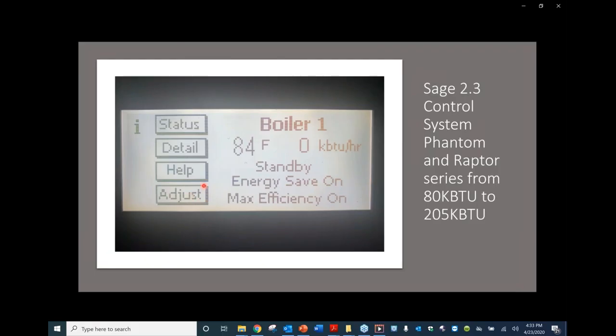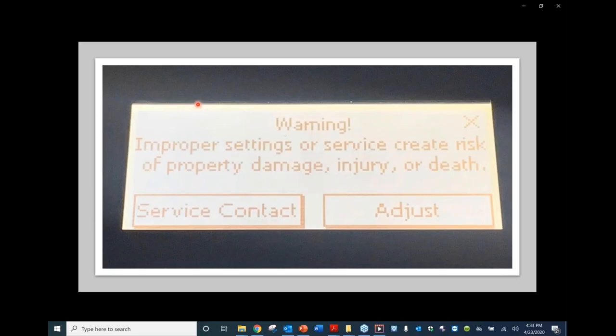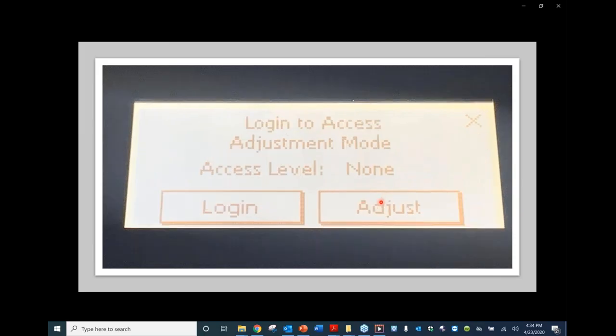In this training, we're going to be going over the adjustment menu. To enter the adjustment menu, we're going to press adjust. Once you press adjust, this screen will show up, informing you that improper settings or service can cause property damage, injury, or death. If you were to press service contact, you would enter in your service contact information, your phone number, company name, etc. We're going to press adjust. When we press adjust, it's going to ask you to log into the adjustment mode of the boiler. Currently, there's no access level, meaning you cannot get in to make any changes. So we're going to press login.